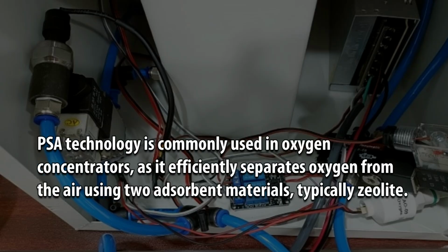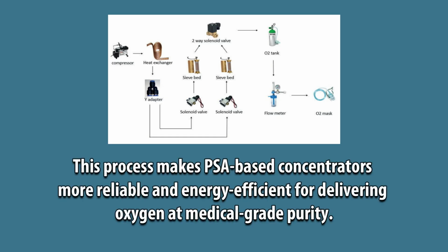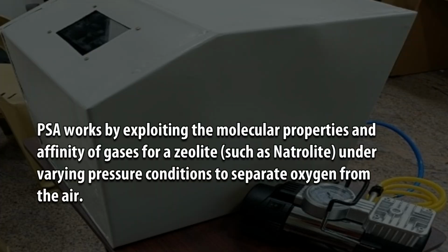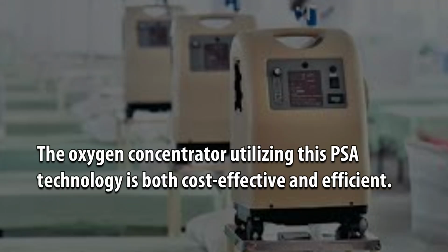PSA technology is commonly used in oxygen concentrators as it efficiently separates oxygen from the air using two adsorbent materials, typically zeolite. This process makes PSA-based concentrators more reliable and energy efficient for delivering oxygen at medical-grade purity. PSA works by exploiting the molecular properties and affinity of gases for a zeolite, such as natrolite, under varying pressure conditions to separate oxygen from the air. The oxygen concentrator utilizing this PSA technology is both cost-effective and efficient.